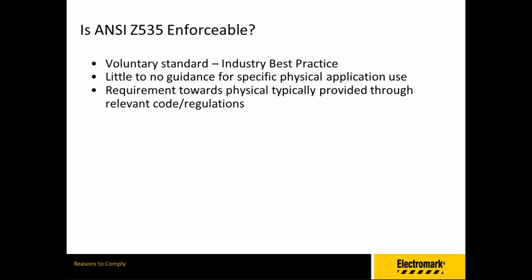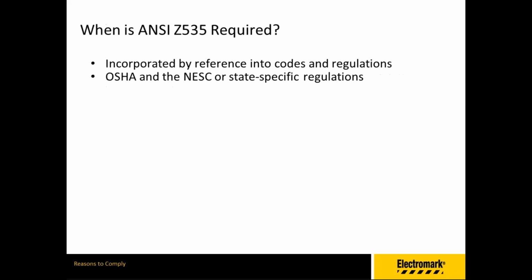Requirements like these are typically provided through relevant codes and regulations that are put forth by, for instance, OSHA or the NESC, just to name two. So conformance to the Z535 standard becomes mandatory, or what I would then call compliance, when it's incorporated by reference into the codes and regulations you have to stay in compliance with.